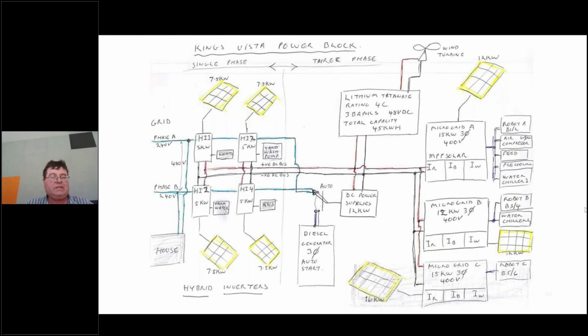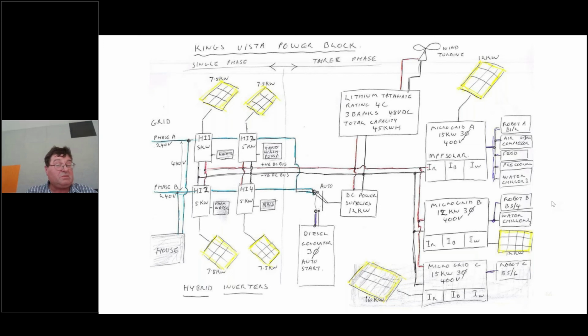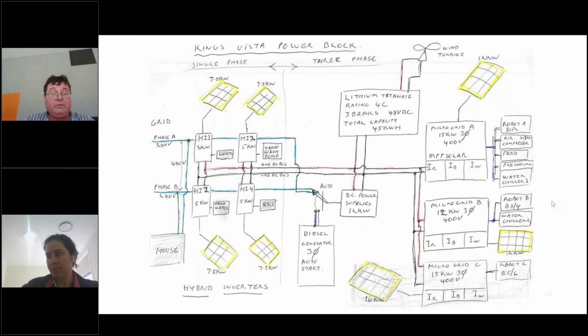I also imported some. Most of that import would have come to the house on the bottom left-hand corner. That's greyed out at the moment because it will be moved to the hybrid inverters that are sitting on the grid side shortly. In the end, pretty much we will run most of the year with very little peak power being used. In winter, I suspect we'll charge the batteries up a little bit in the morning to just cater for that first bit of peak power in the morning. But at the moment, on days like we've got today, we were off the grid from 7 o'clock this morning and won't go back onto the grid. Might not even need to go back onto the grid tonight.